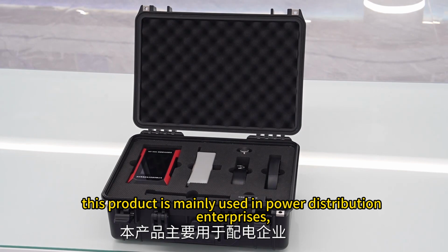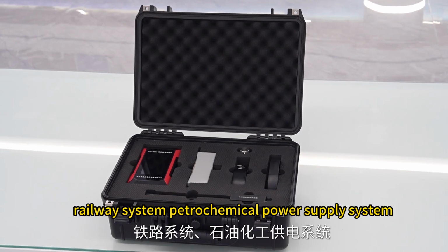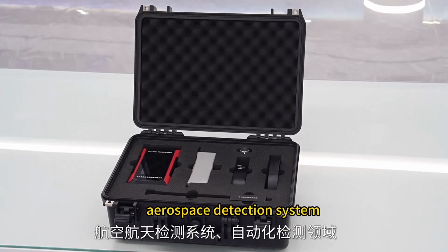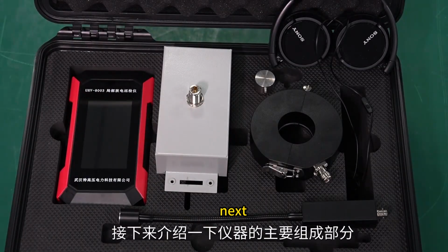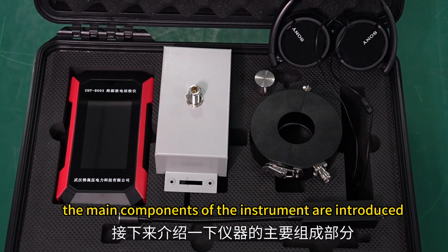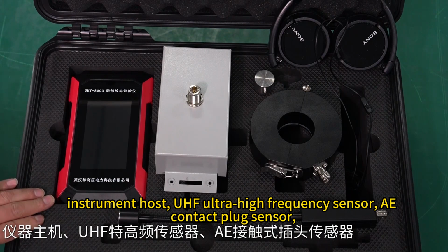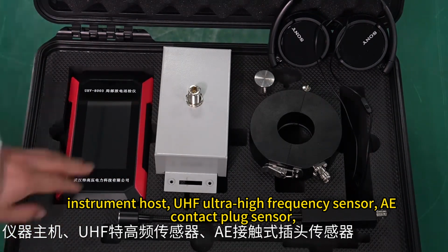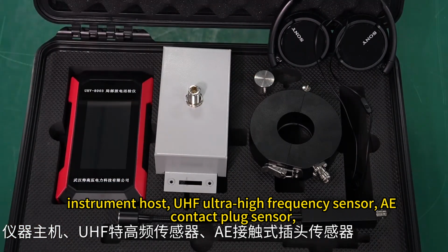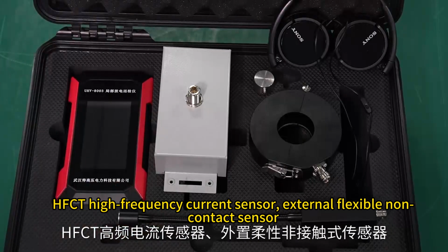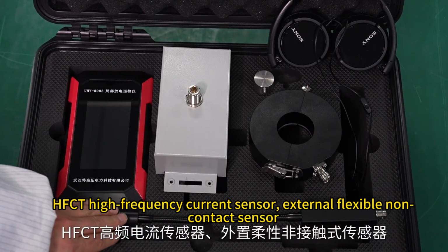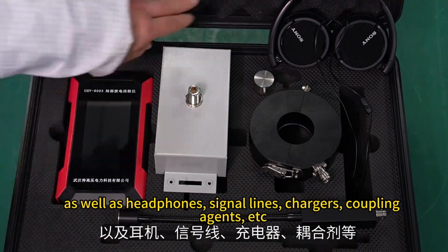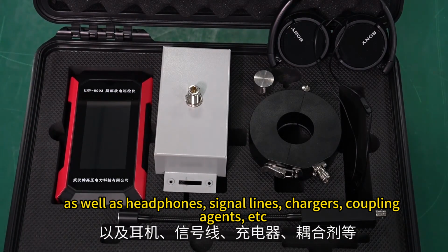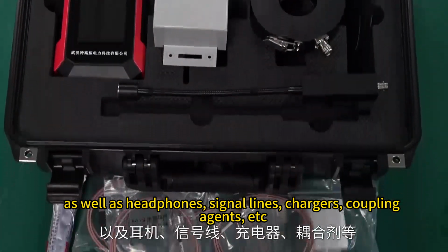This product is mainly used in power distribution enterprises, railway system, petrochemical power supply system, aerospace detection system, and automated detection field. Next, the main components of the instrument are introduced: instrument host, UHF ultra-high frequency sensor, AE contact plug sensor, HFCT high-frequency current sensor, external flexible non-contact sensor, as well as headphones, signal lines, chargers, coupling agents, etc.